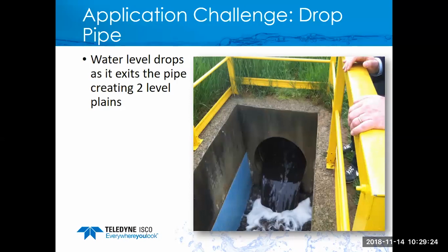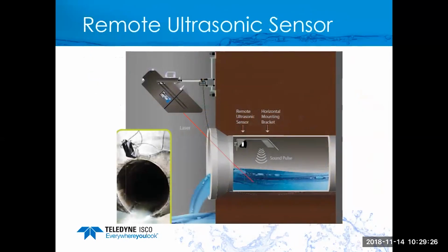So that wasn't going to work. So what we did is we made some changes to the laser and some enhancements. You can order a laser with a built-in ultrasonic, or what we call remote ultrasonic. What the remote ultrasonic does is it's mounted on a bracket, typically horizontally, and it deflects off the bracket. Now it measures flow or level and velocity in the exact same location.